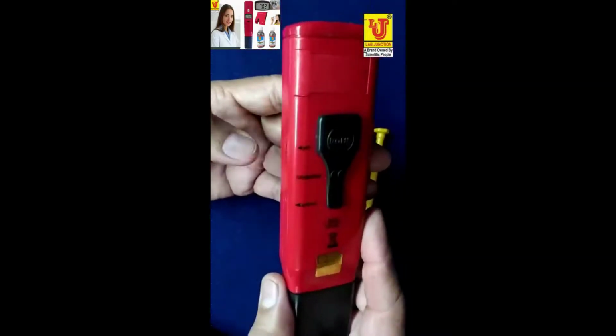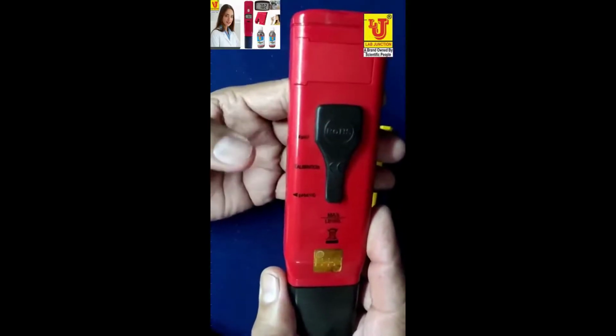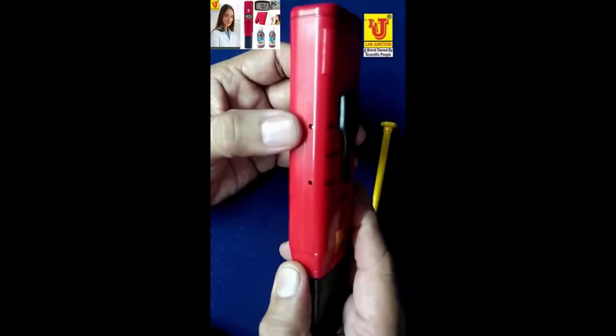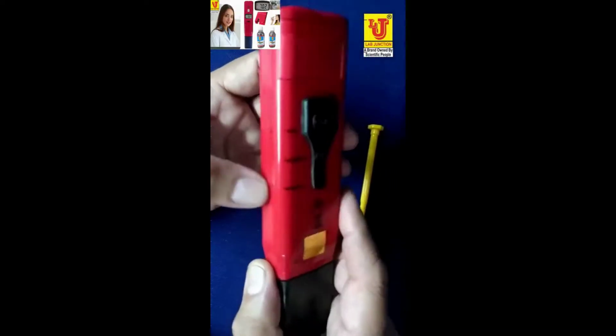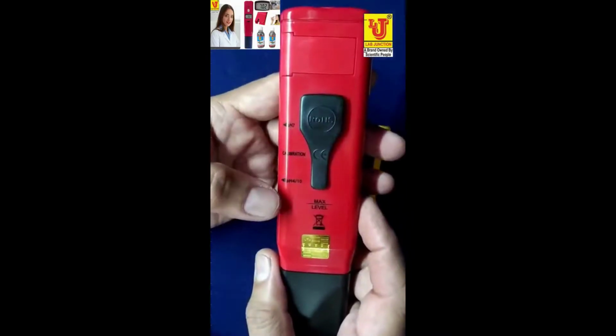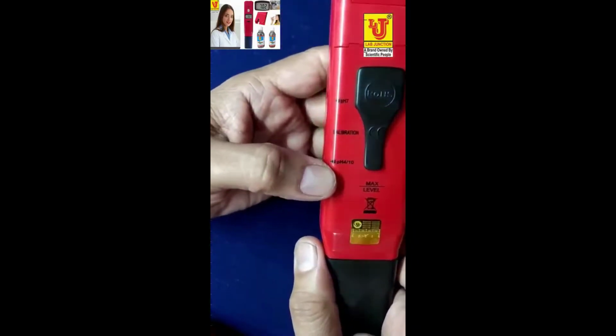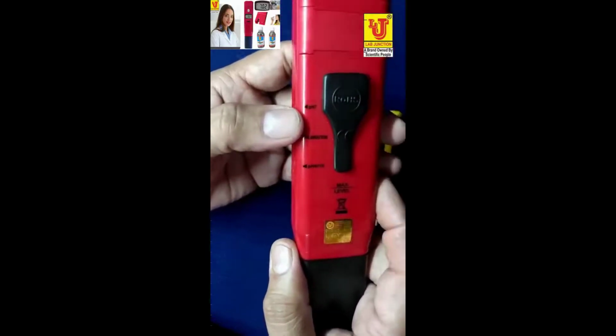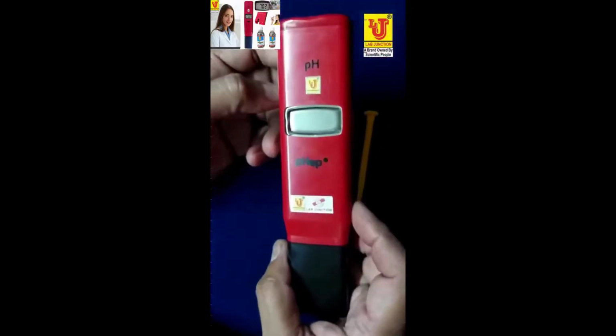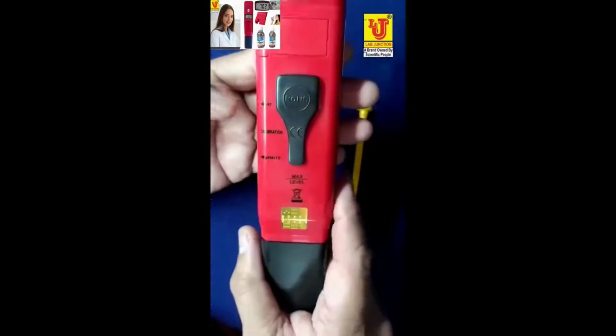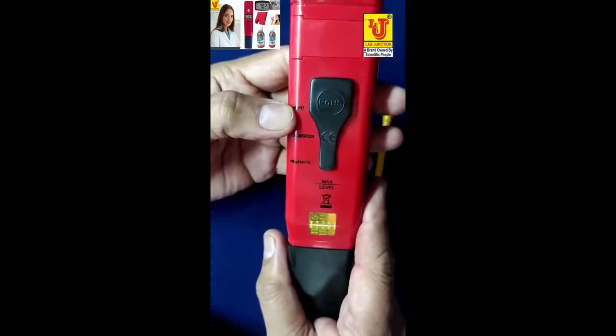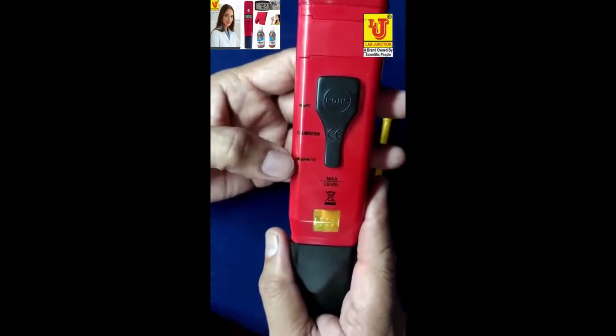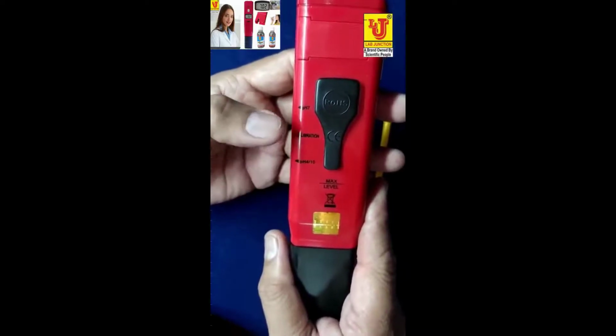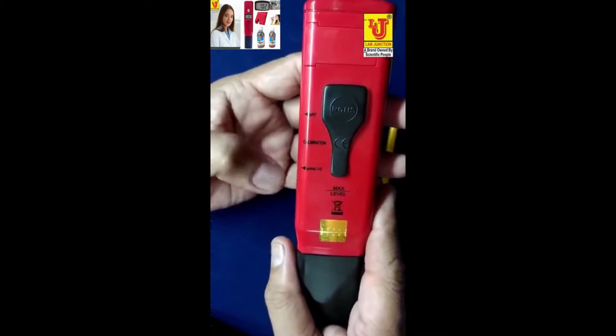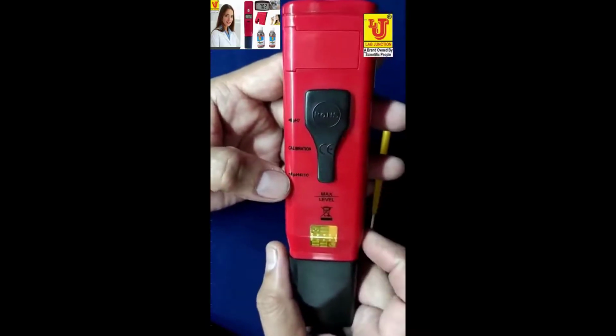In this, these are the calibration screws, like pH 7, pH 4 or pH 10. You can calibrate only a single buffer because this is a single calibration pocket size pH meter. You can calibrate pH 7 or pH 4 or pH 10. You can calibrate only a single buffer, then the other buffers are already calibrated.